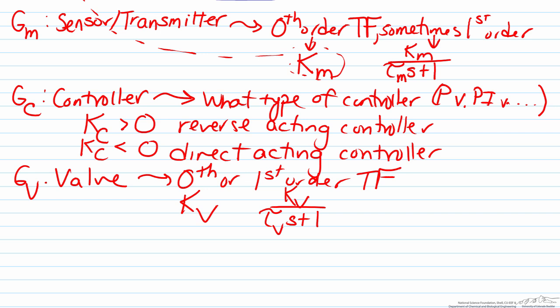And again the determination about whether or not it would be necessary to include these time constants for both the sensor, the valve, and the process which I will describe later is how quickly it takes for changes to be made. In most situations the sensor transmitter dynamics can be neglected because they are much faster than the valve and or the process.